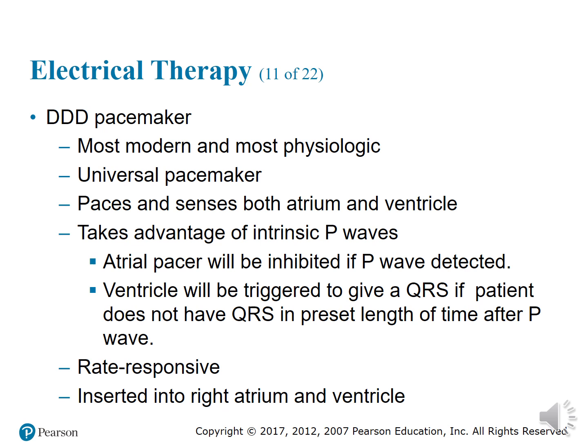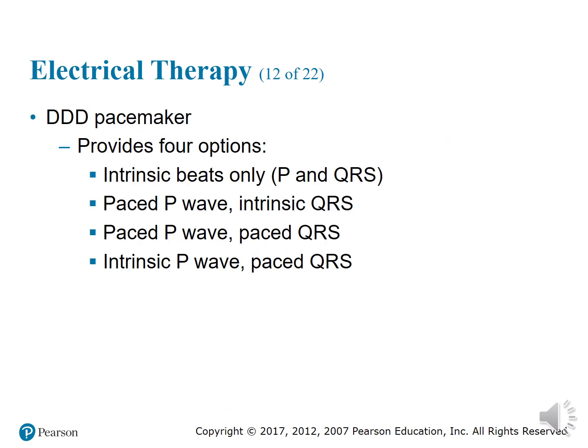and the ability to sense and pace the atria and ventricle at the same time according to the intrinsic atrial rate and the maximal rate limit. The DDD pacemaker senses intrinsic atrial activity and takes advantage of the patient's own P wave. DDD pacemakers are usually rate responsive, meaning that they will provide a paced QRS to follow the patient's intrinsic P wave within preset heart rate limits. These limits are usually 60 to 125 beats per minute. The DDD pacemaker will not provide a paced QRS for each intrinsic P wave because that would result in a tachycardia, which is dangerous to the patient.